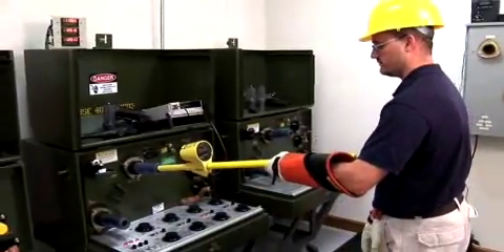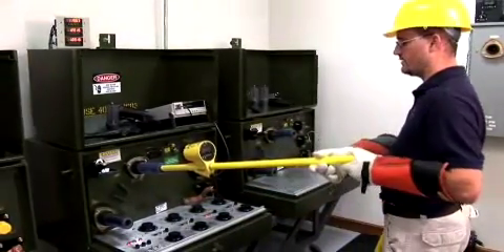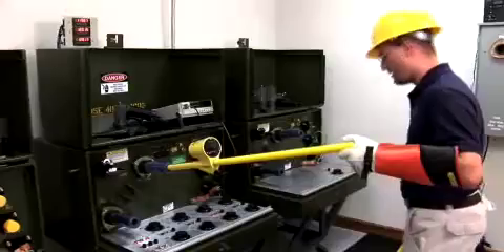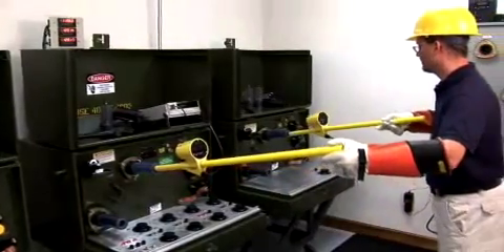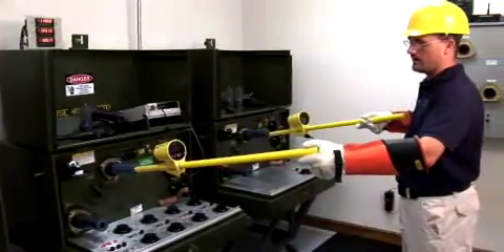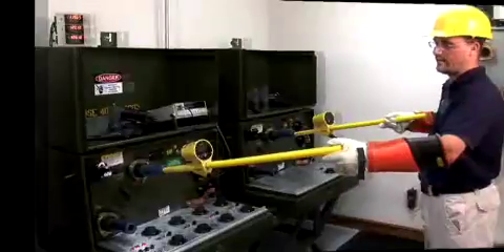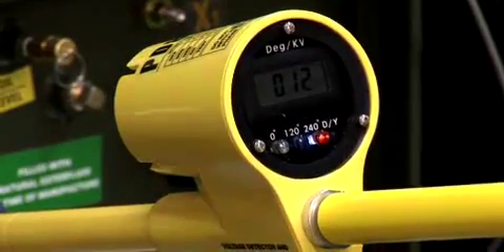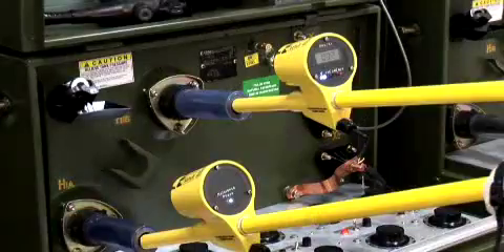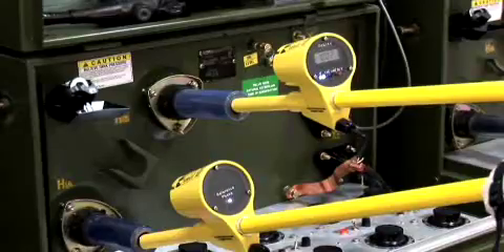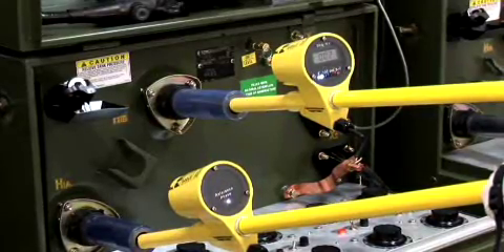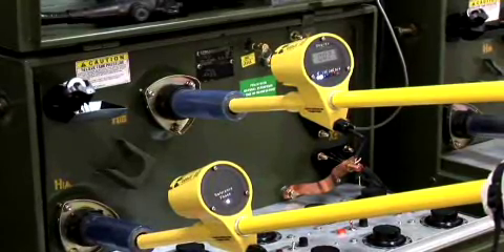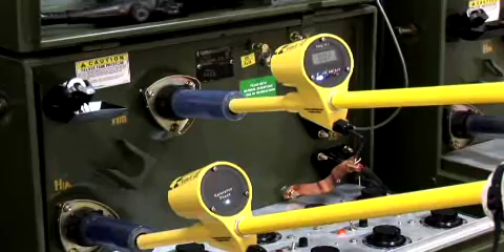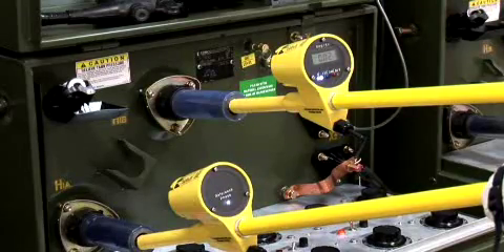You can also phase by voltage. We verified that each transformer is energized. And we'll put both probes. Now we're representing 12 kV and a red light, which is obviously out of phase, over to the other bushing. Now we're measuring approximately 0 volts. We have two white lights indicating that the two bushings are in phase.